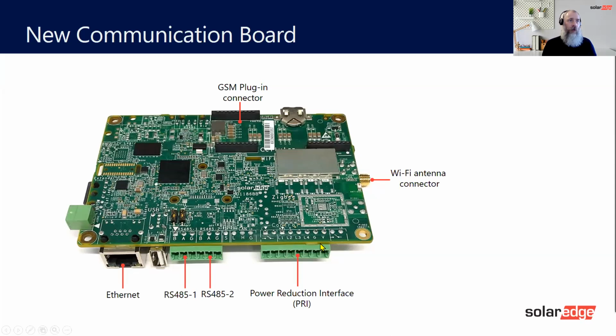Coming down to the bottom, we have what we call the power reduction interface. This allows the inverter to be controlled remotely. It could be from a utility company via a GSM device, where the utility company tells the inverters to turn off or to power down. Or you could link it into your diesel generator, a backup generator, so when the backup generator comes on, the inverter will reduce power. It does this either by turning off completely, so the AC remains on but the power is reduced, or we have 100%, 60%, 30%, and off. So they're the different stages. Utility companies can reduce the power of the inverters from 100% production at the time to 60%, 30%, or off.